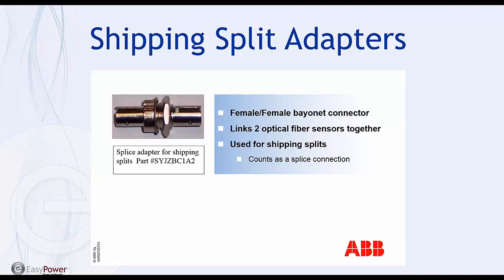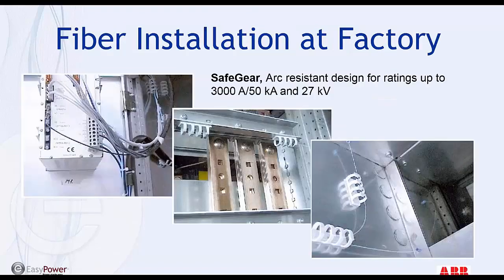Now let's take a look at how we're going to install these. Right here are pictures from our newest switchgear line called SafeGear, which is an arc-resistant design. There are also many other benefits to this switchgear, and it was just displayed at the Automation Customer World Trade Show in Houston. You have the IEC 61850. You have the sensor technology, and there's a lot of other things, and it's certainly beyond the scope of this webinar. But if you ever have a chance, check that out.